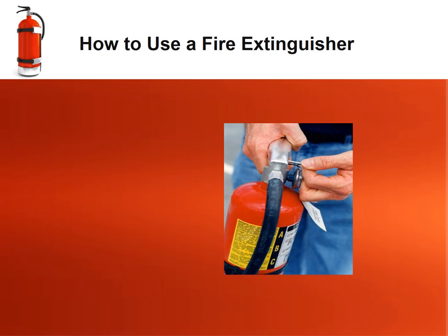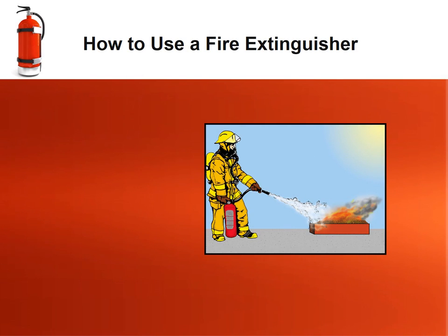The P in PASS stands for pull the pin, which allows you to discharge the fire extinguisher. The pin prevents accidental discharge from squeezing the handle. Next, aim at the base of the fire, preferably about six inches below or under the fuel, to avoid blowing or scattering the fuel around. If you aim at the flames, the extinguishing agent will fly right through without stopping the fire.